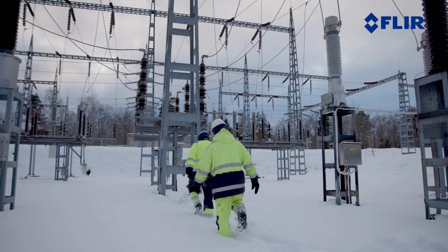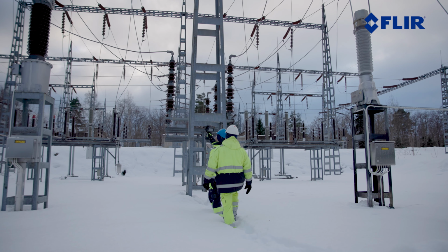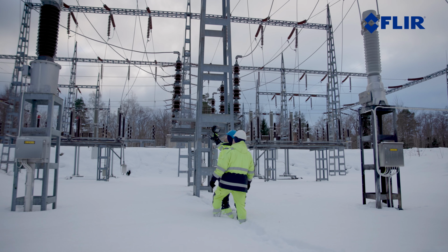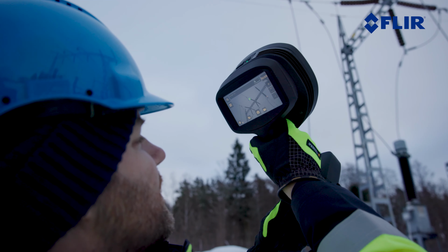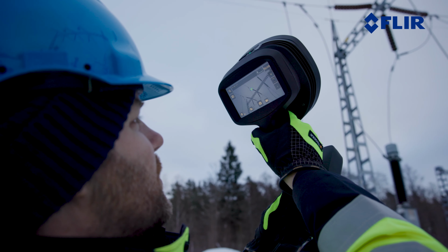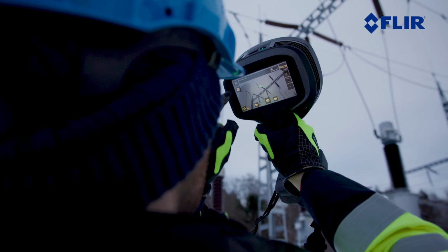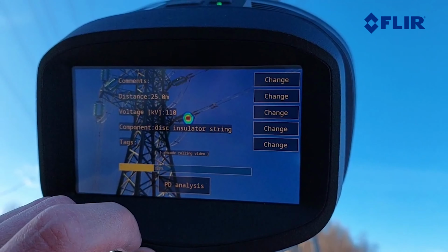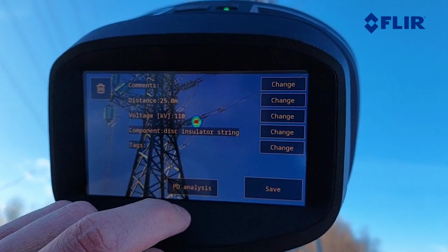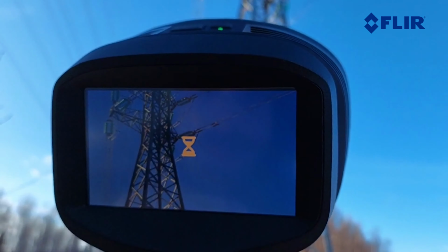With its 124 microphones, the ultrasonic FLIR SI2PD acoustic imager can accurately detect signals that partial discharges emit from up to 200 meters away. The device then displays the phase-resolved partial discharge pattern, or PRPD, which depicts the type of the PD. The advanced AI-driven on-device analytics identifies the fault type and provides information of the severity of the fault immediately for in-the-field decision support.